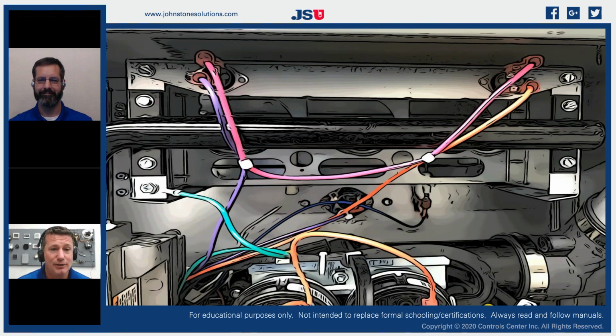The next time you look at a furnace, you're going to see it differently. You're going to see two components to this circuit, and it'll be the same way in every hot surface ignition gas-fired appliance that you will ever encounter. You're going to see an isolated flame rod and a dedicated ground wire. That dedicated ground wire goes directly back to the control board. It doesn't stop anywhere. It goes directly from the burner box surface to the ignition control board.